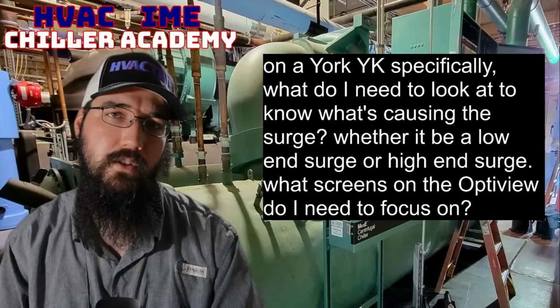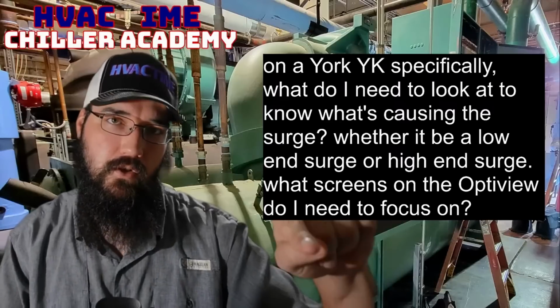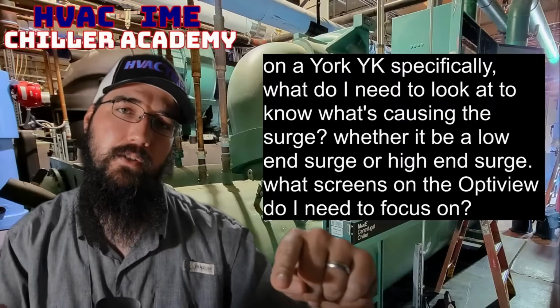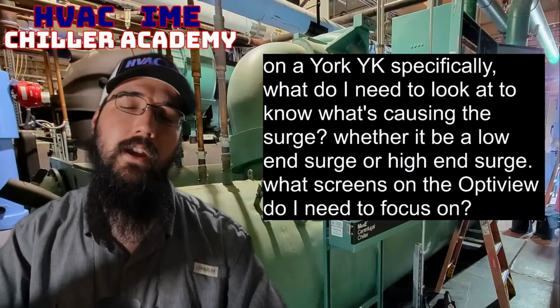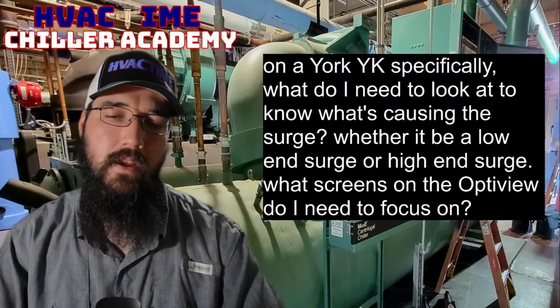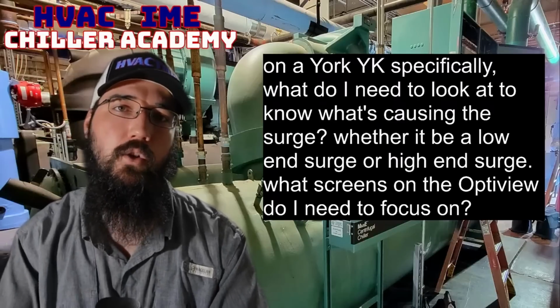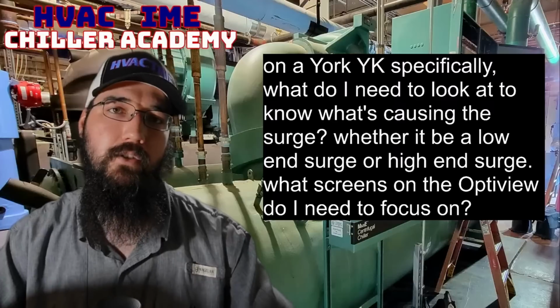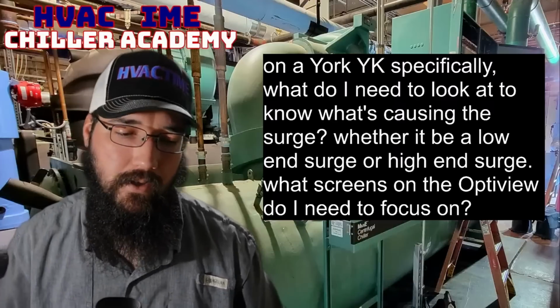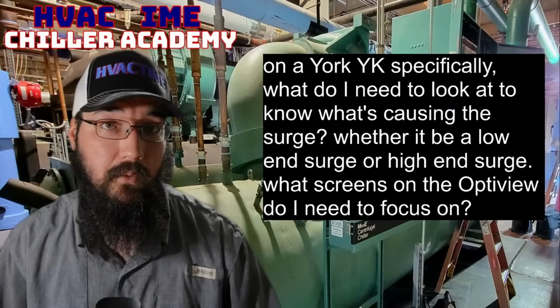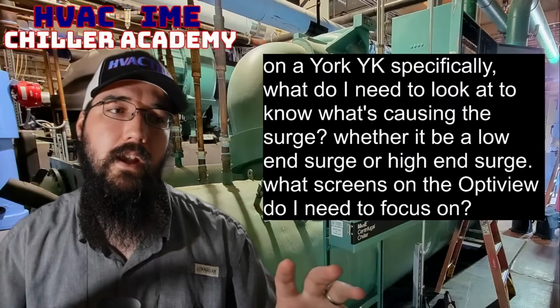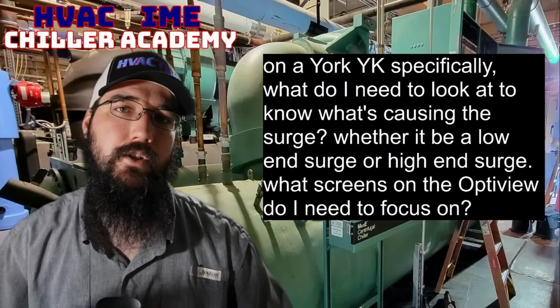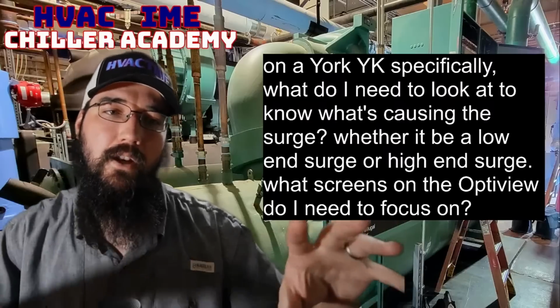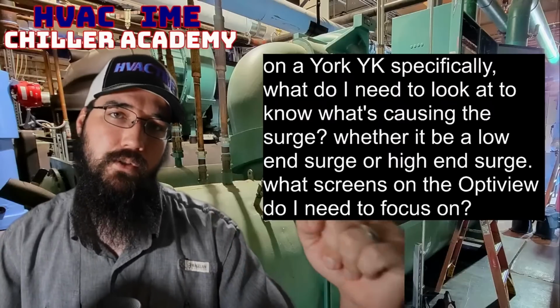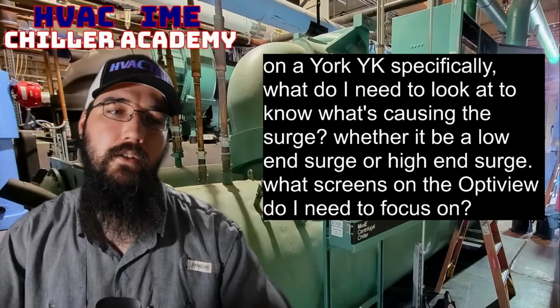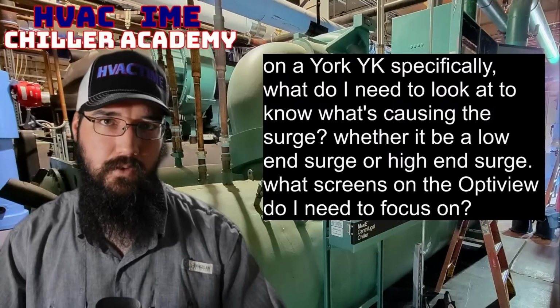So when you go to the compressor or the VGD screen and you see the stall voltage, that is the output coming from the stall detection board that's reading that discharge transducer. And then it's determining how close we are, or how much instability there is. So you can think of that value as a stall detection. So that's really helpful if you're in a mild surge condition. It's not too severe, but you're trying to kind of make adjustments as you go. That voltage value can really help you determine if there's an issue somewhere.